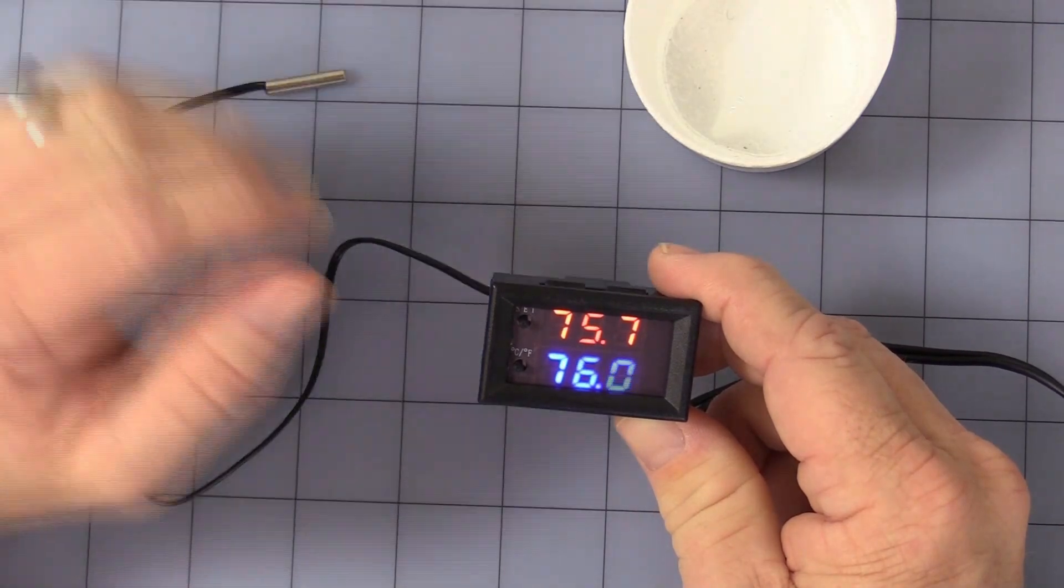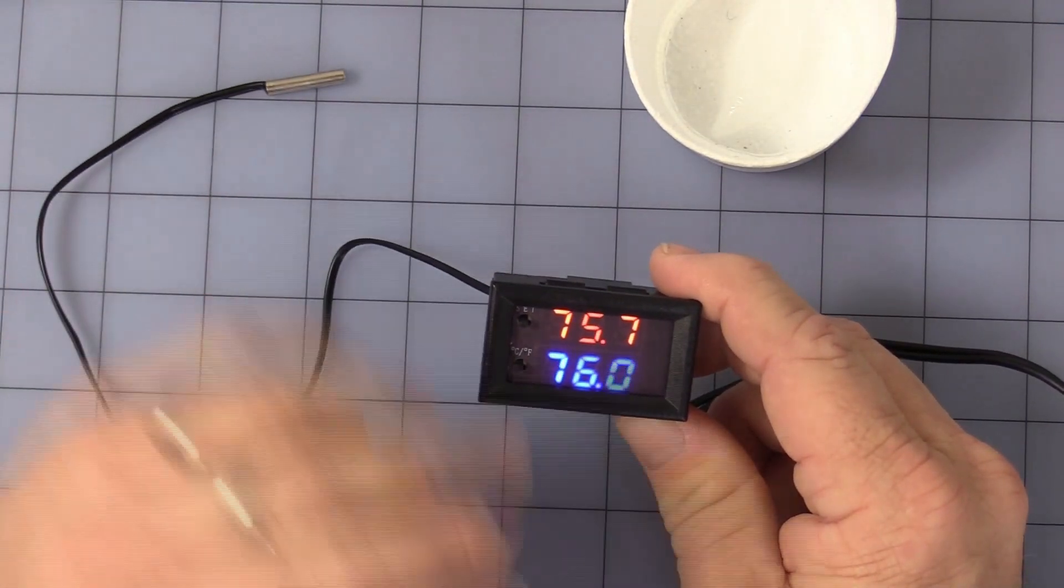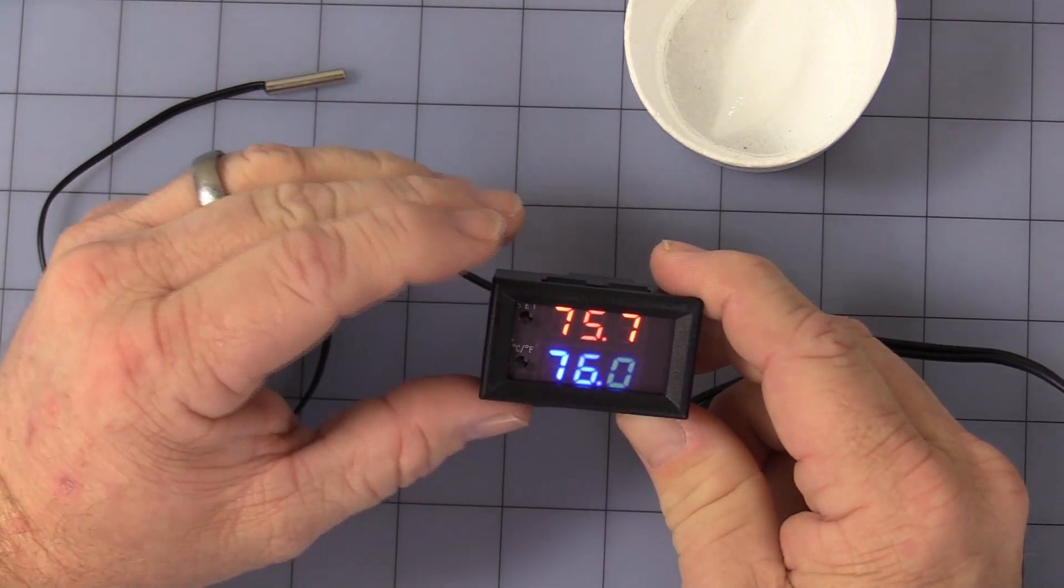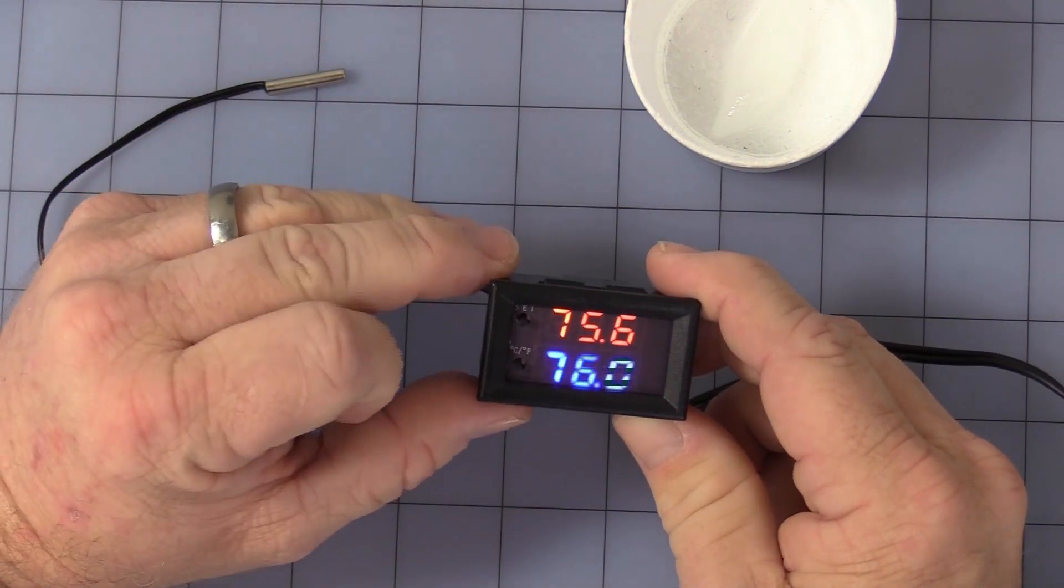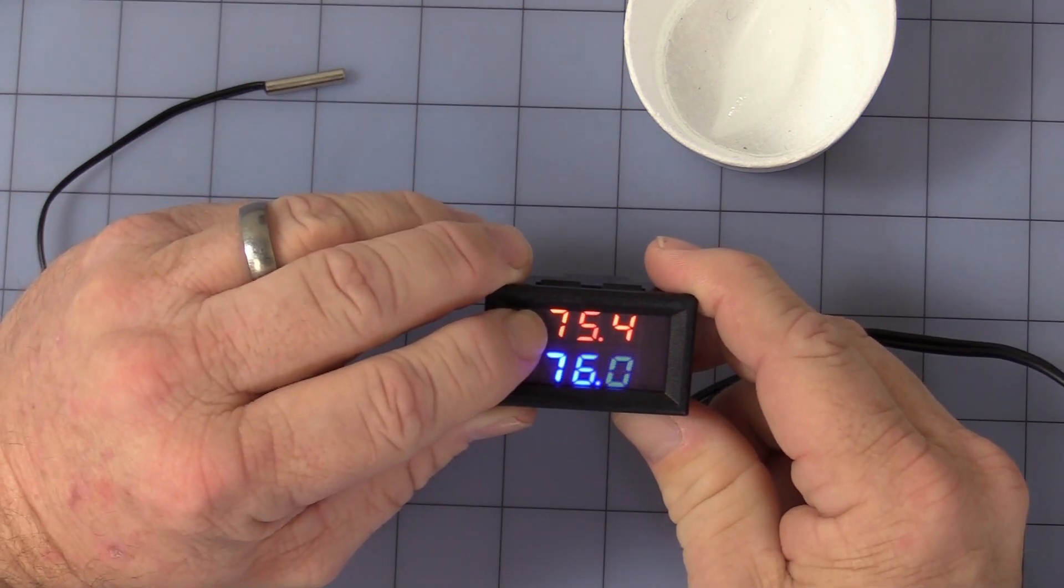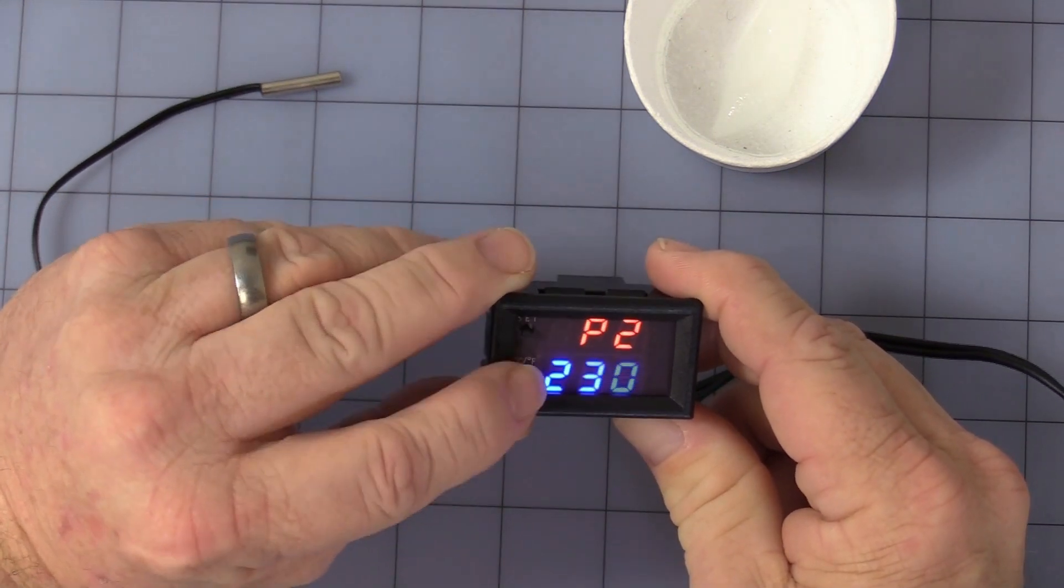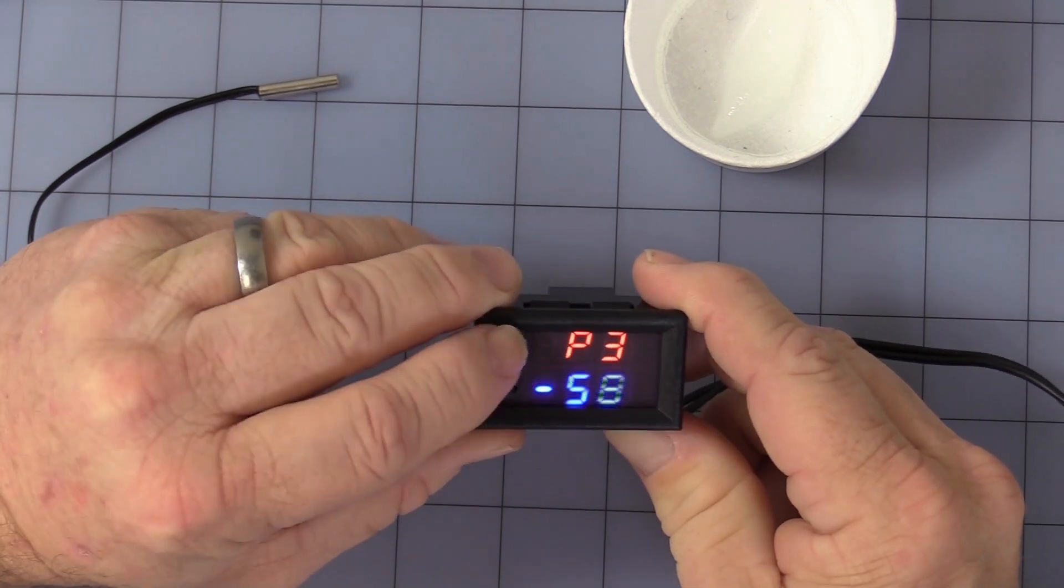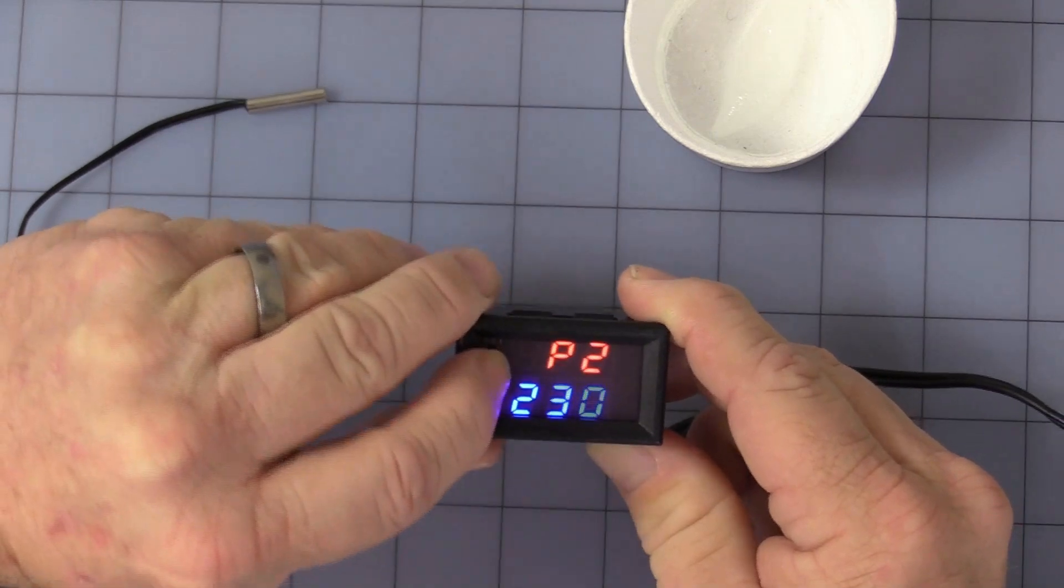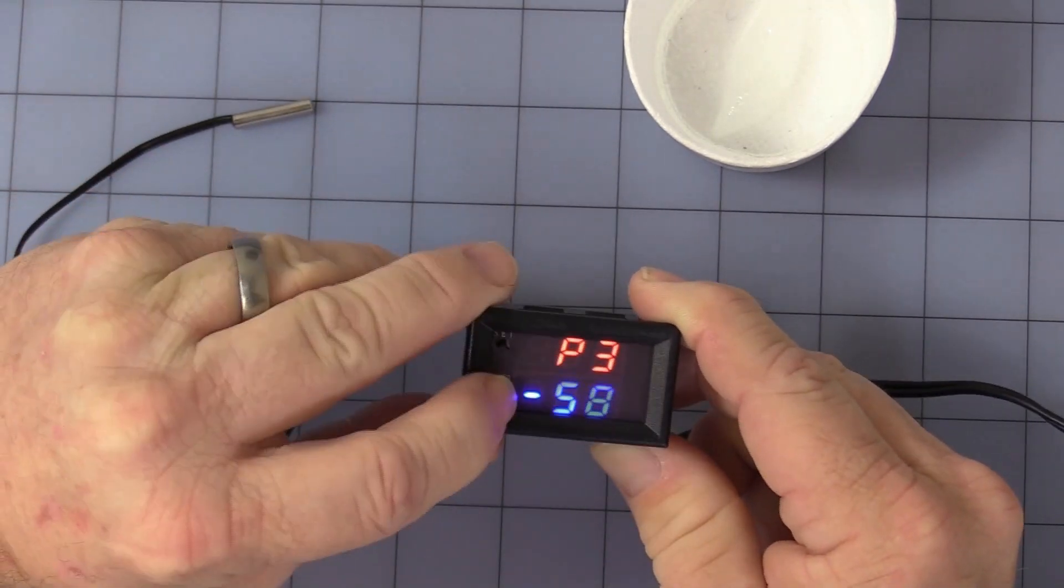Now, we get into P2, which is just a kind of a safety feature. It's a high set limit. So, no one can accidentally adjust the temperature too high on you while you're running the program here. So, you press and hold. Go to P2. You can see factory sets 230 degrees Fahrenheit.